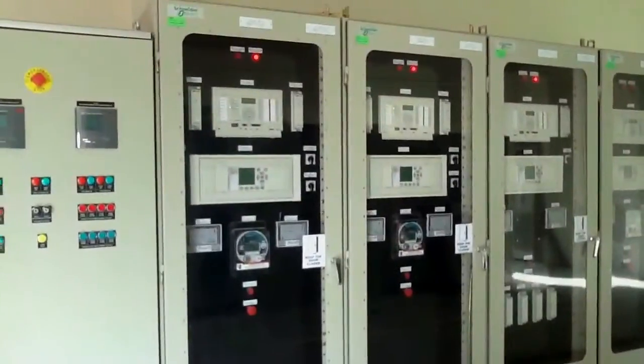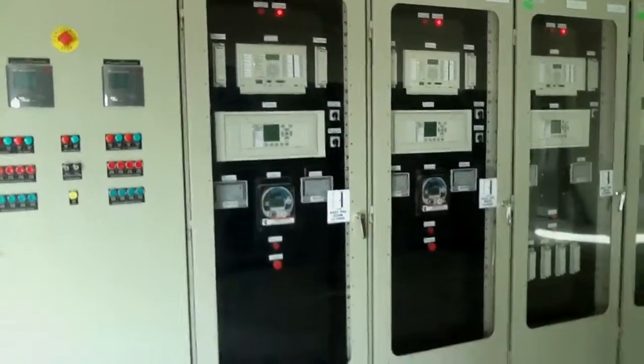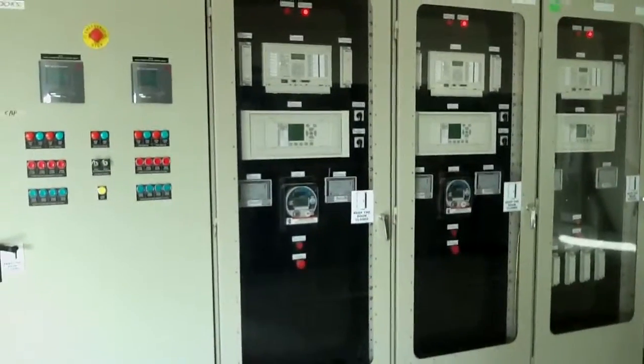And these are their protection relays and their control panels. From here we can close and open the circuit breakers. There is interlocking present in between the circuit breakers so that if there is any fault, the circuit breaker can operate according to the logic which we have developed.